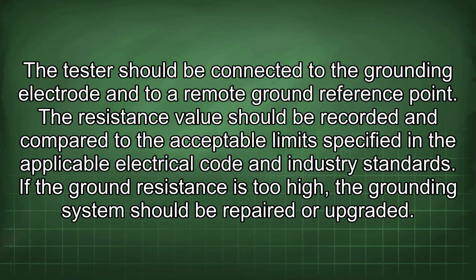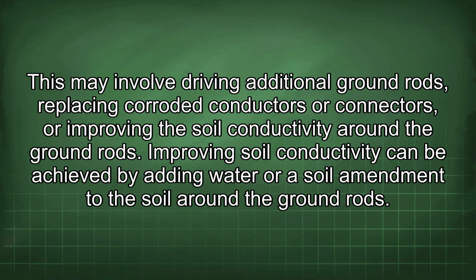The resistance value should be recorded and compared to the acceptable limits specified in the applicable electrical code and industry standards. If the ground resistance is too high, the grounding system should be repaired or upgraded. This may involve driving additional ground rods, replacing corroded conductors or connectors, or improving the soil conductivity around the ground rods. Improving soil conductivity can be achieved by adding water or a soil amendment to the soil around the ground rods.